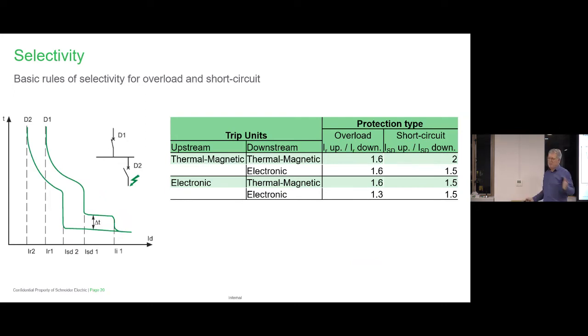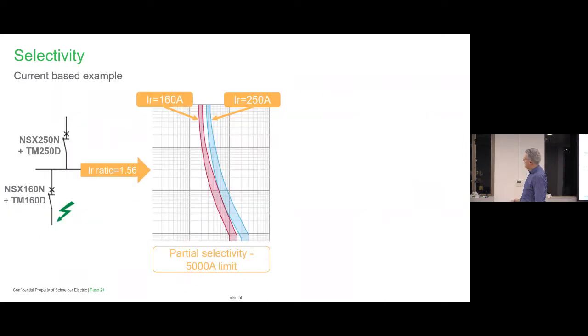That's probably to be expected, because the electronic trip units have got more adjustability on their trip units. So that's how we get better selectivity. And a good example of this is here. I'll just show this. So between these two, you can actually go on your calculator or something like that, but there is 1.56 times between these two in terms of the IR ratio. It's not 1.6. And because of that, if we went into our tables and you went into one of our electronic tools, it would say you've got partial selectivity up to 5 kA.